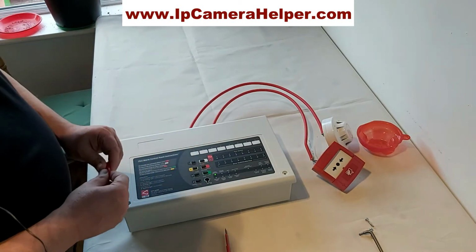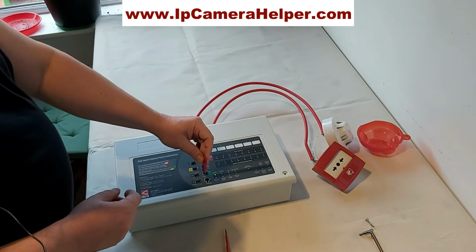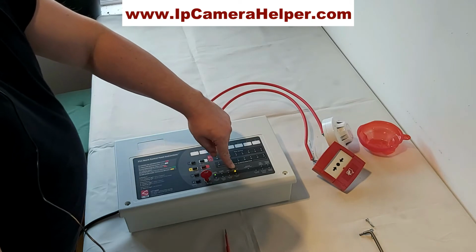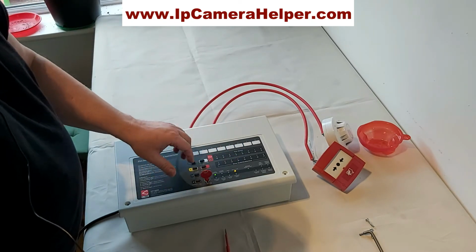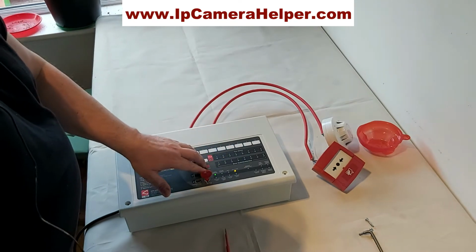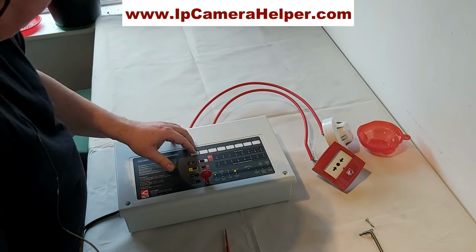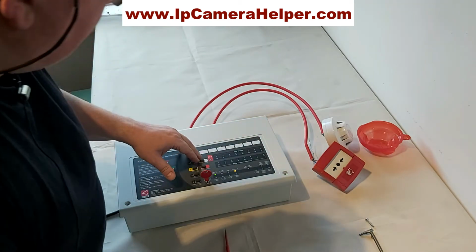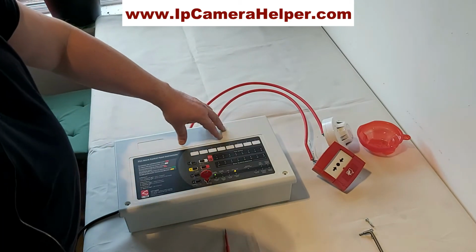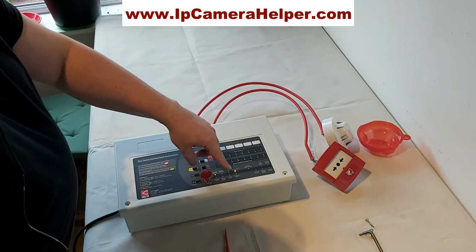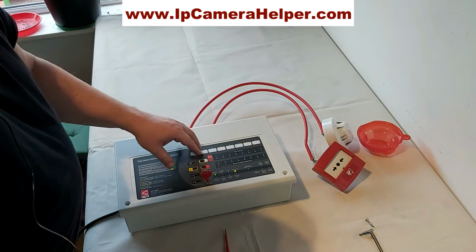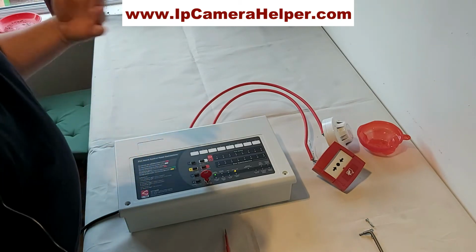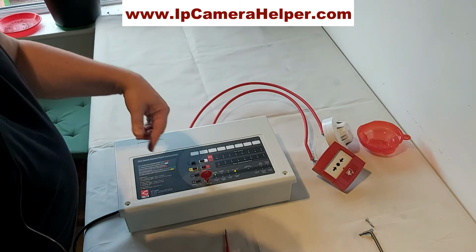To access controls on this fire panel, you have to have a key, and you turn it to position 1, and then it says accessed, so it means you can press those buttons here. Three main buttons which any regular user will be using. First is silencing the internal sounder. There's an internal beeper, the buzzer, however you call it, which will be beeping when a fault is on. One of the faults will show up. You can silence that, just that way you do not restore the fault, you just acknowledge the fact that you know.